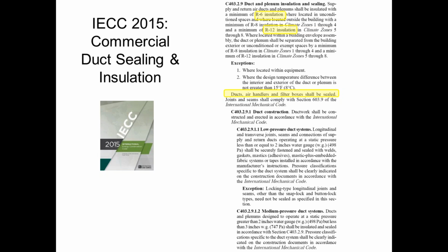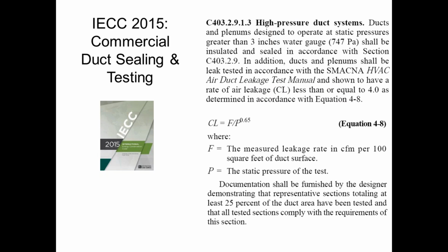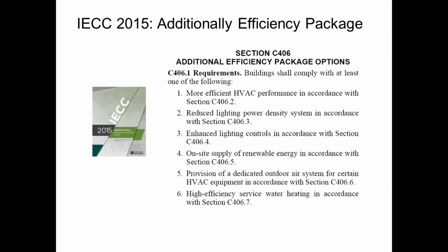All ductwork has to be sealed. Ducts, air handlers, filters, everything have to be sealed, right? For low and medium pressure systems, you have to seal them, but you don't have to test them. If you go to a high pressure system, which means 3 inches and over, you've got to seal them and test them. That's probably not a rooftop anymore. So for rooftops, you've got to seal the ductwork and insulate the ductwork, but you don't have to test the leakage. Bigger systems, you would have to do that.